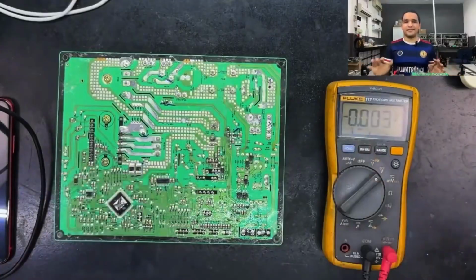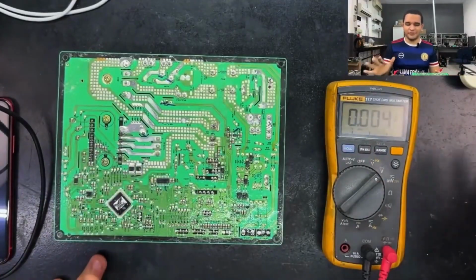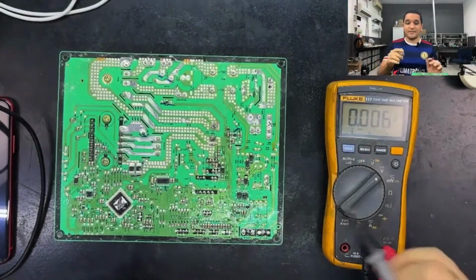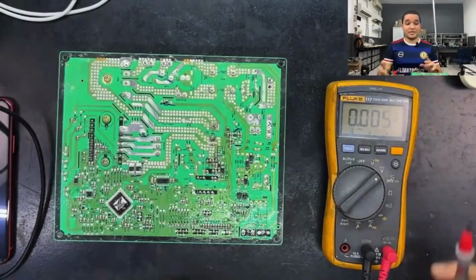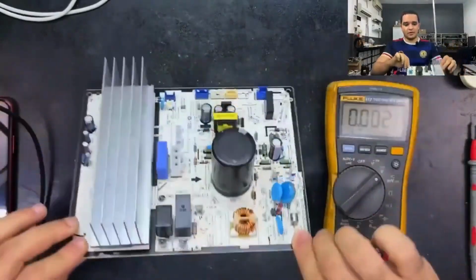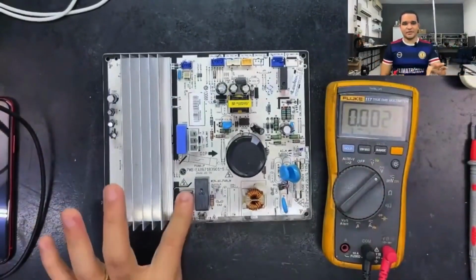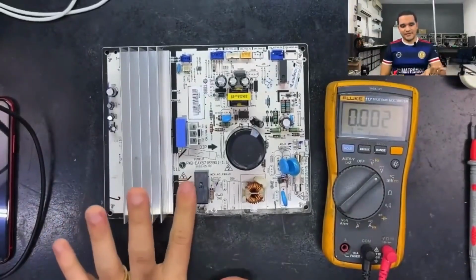Measured here, there's no tension or it's low. As I mentioned, if it's absent, the error won't show. It must be low. If it's low, the error will appear, and that's right. In this case, what could it be? What would I analyze? I would check if this component here is heating up. This component here is the PTC. I would check if it is heating up.